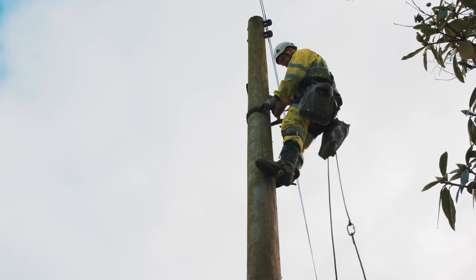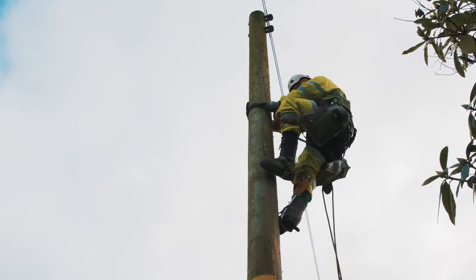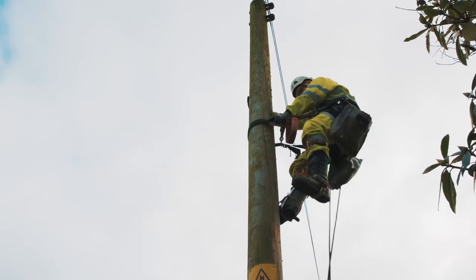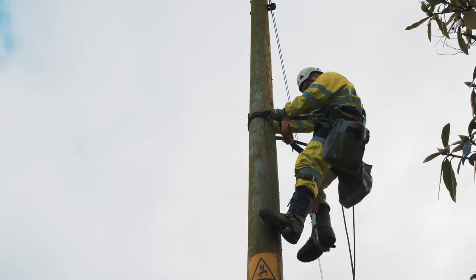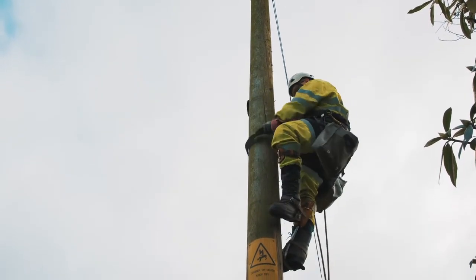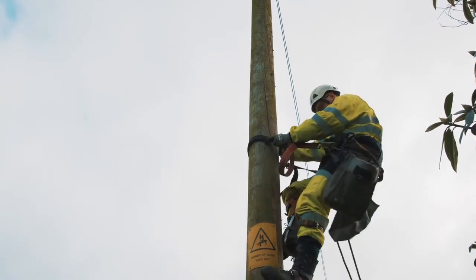Apart from actually being able to reduce customer minutes lost in terms of your high current, low impedance type faults, it's better customer service. You're removing danger from staff going out to identify and locate these faults. But the most important thing is the safety. Basically, this system could prevent the loss of life where a low line scenario occurs. This is one of the most dangerous situations that can be posed.